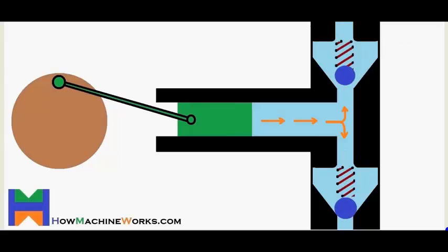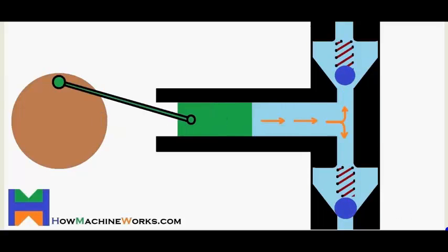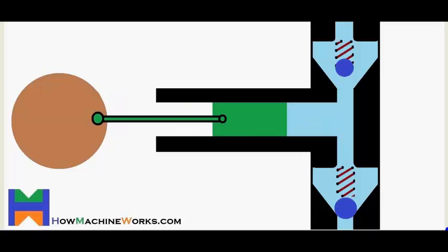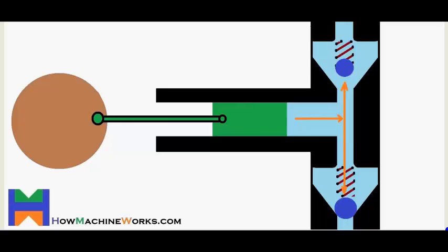And as the outlet valve opens up, the oil can escape over there. You can see further the rotor is rotating and the plunger moves further towards the front, which pushes the oil outside through the outlet. So that's how the discharge is happening in a plunger pump. This is called a positive displacement pump because whenever it rotates there is a discharge.